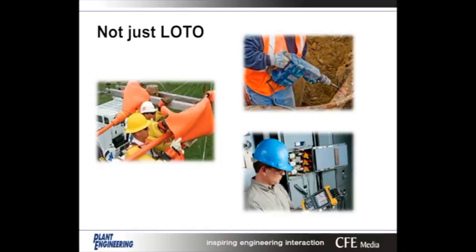We have the worker with the electrically powered tool - again, lockout-tagout is not an effective control for that type of exposure. And we have a person doing diagnostic testing on energized systems, where lockout-tagout is again not an effective solution.